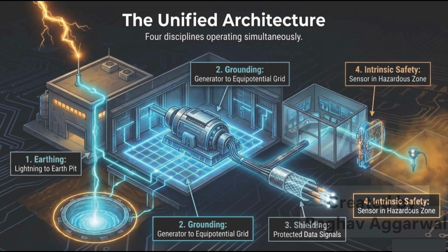Let us recall all four protection disciplines into one integrated safety architecture. First, earthing directs high-energy events such as lightning safely into the earth. Second, grounding establishes a common reference through an equipotential grid, helping systems operate correctly and safely. Third, shielding protects sensitive data signals from interference, ensuring accurate communication and measurement. Fourth, intrinsic safety protects sensors and devices operating within hazardous zones by restricting available energy. Although each discipline addresses a different type of risk, they work simultaneously throughout the plant.